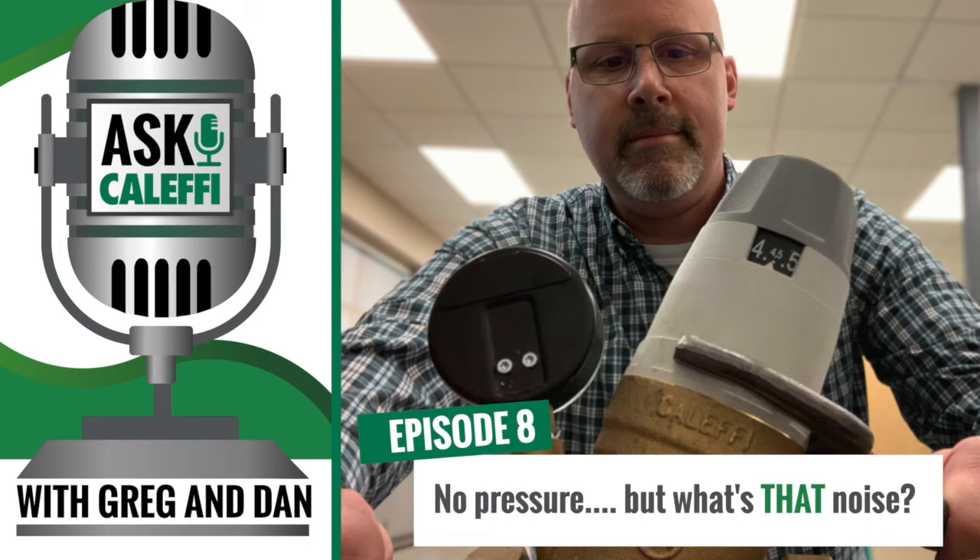Oversizing is usually the biggest trouble. That valve is going to be noisy — a lot of vibration, shuddering, clunking, or water hammering sound because it's always working at the minimum. In a home where you can hear the valve, you're going to notice it. If it's located in a mechanical room, garage, outside, or in a basement, the homeowner may not hear that sound. But that valve will wear the seat down. So going through and really looking at the sizing chart is a pretty big deal. Number one, most important thing: know your flow rate, know your flow requirement — do not focus on pipe size.